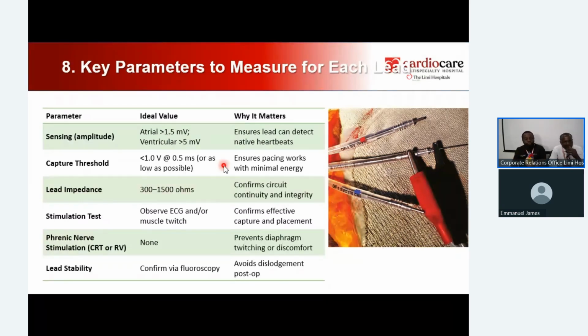That's great. And then for stimulation testing, we also check to see how it changes on the ECG. So we'll start pacing, and then we'll see whether the ECG is showing that it's capturing, and that there's no muscle twitching as well. We do this using the cable, the pacing cable. You can see it in the picture there.